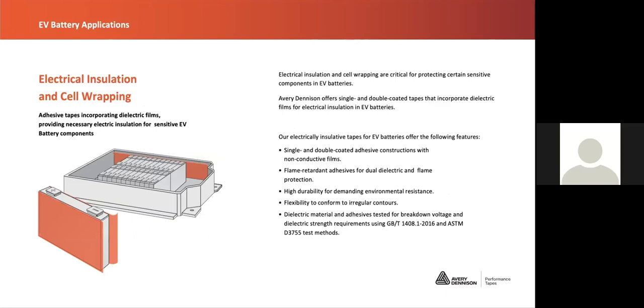We have both single and double coated tapes that incorporate these dielectric films, as Scott has talked about already, where double coated tapes are typically combined with other materials such as the compression pads to achieve that electrical insulation and combine the adhesion. And then we have the single coated tapes that can be applied to things like rigid materials such as aluminum chiller plates or metal structures, aluminum or steel, to give them dielectric strength to protect them from arcing and shorts.